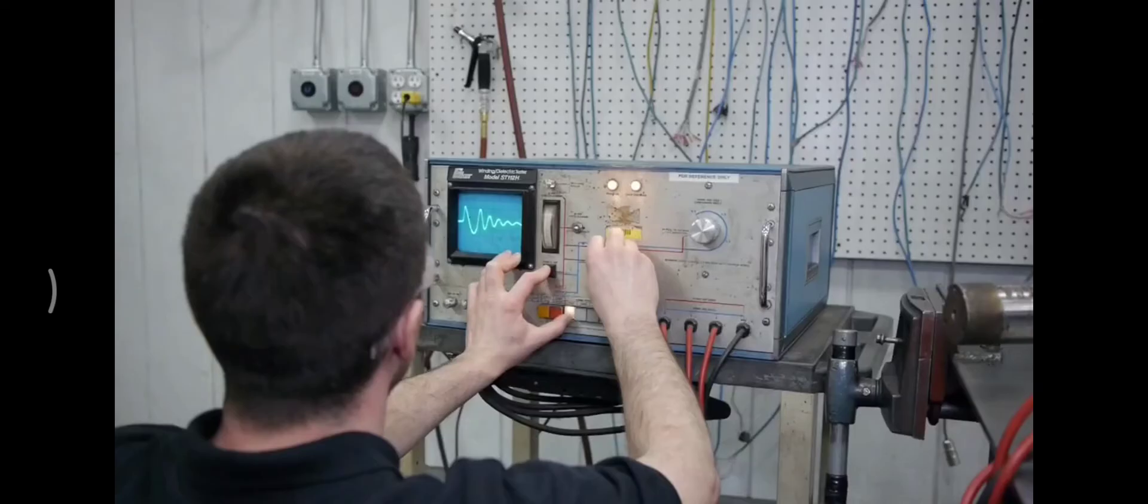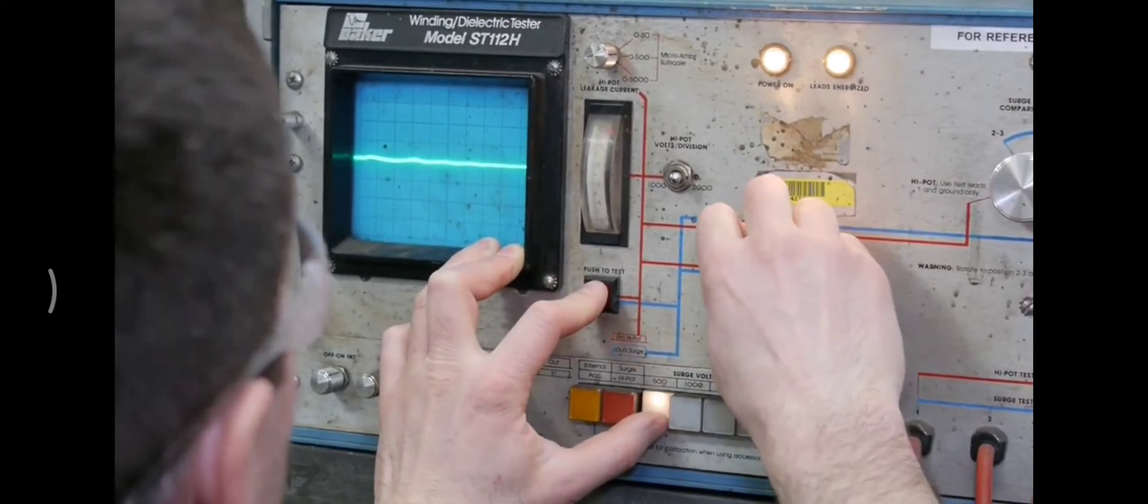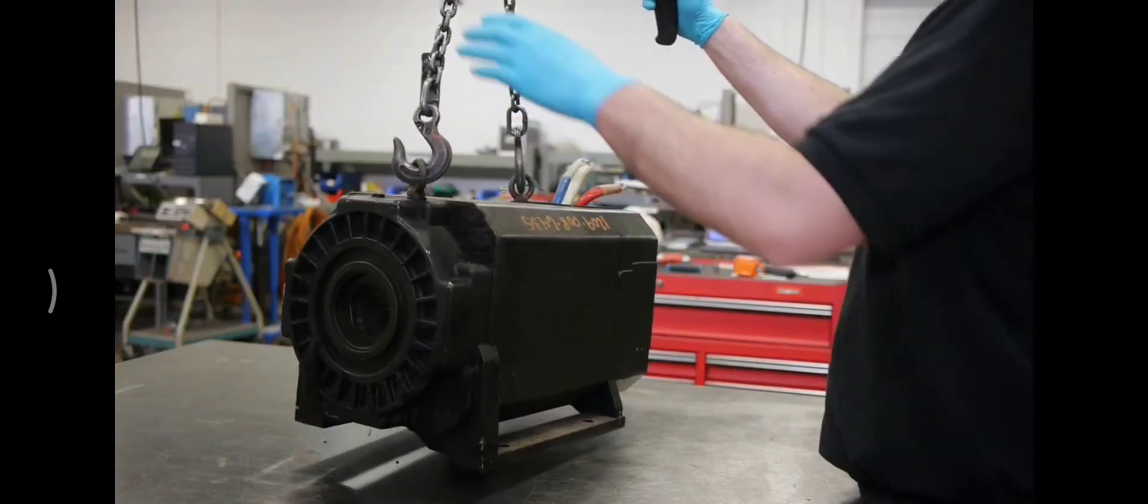The stator is then surge tested as well, where all three phases are tested for dielectric strength of the insulation. In this case, the stator was good.